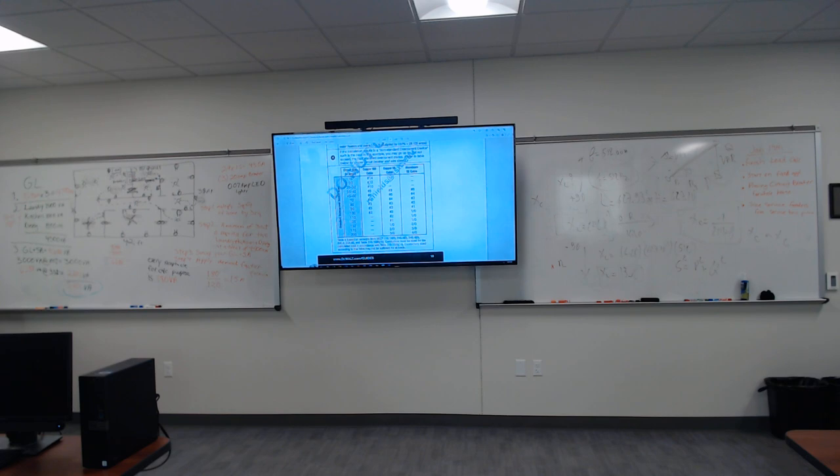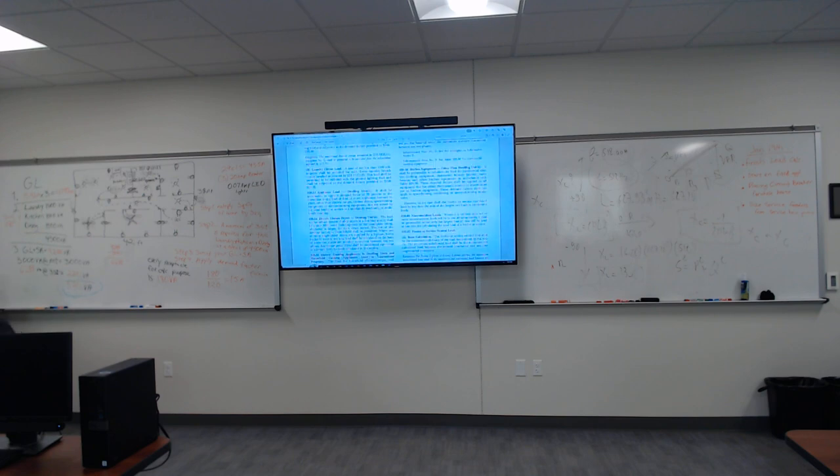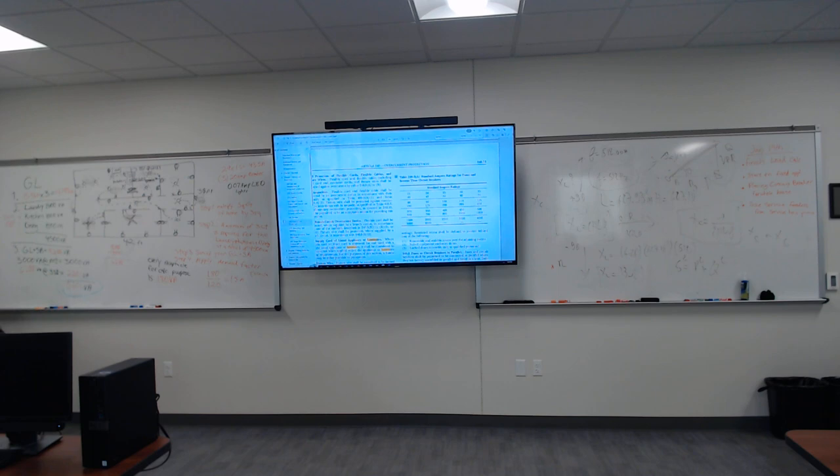But let's go and see exactly where. Hold on. All right, what article, fellas, do we go to size our circuit breaker? Article 240.6. Y'all remember that? 240.6, y'all don't remember that from NEC? Overcurrent protection, y'all remember this table right there. So 175 is in there, so we can select a 175 circuit breaker. All right, let's continue with those questions that they have for us.